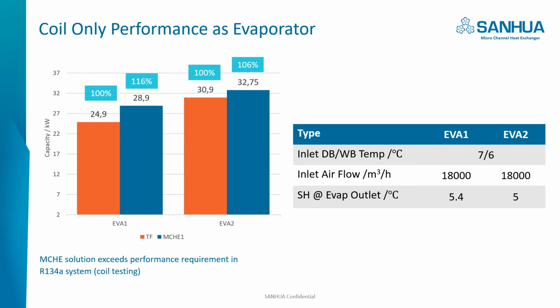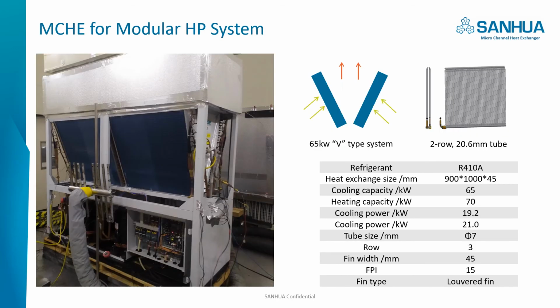Both conditions, microchannel is about 6 to 16% higher than the target. For the system level, we validated the microchannel performance in the modular scroll heat pump system. This is a 65 kilowatt modular heat pump, very popular in China. The original fin tube heat exchangers are 4 pieces, 2 on one side and another 2 on the other side, so they formed the V shape.